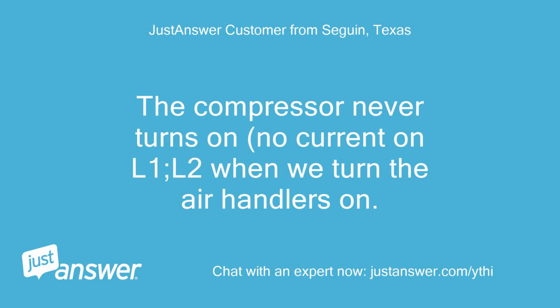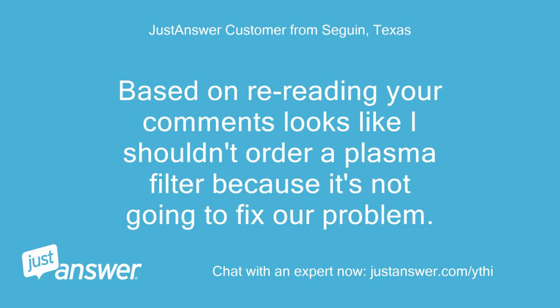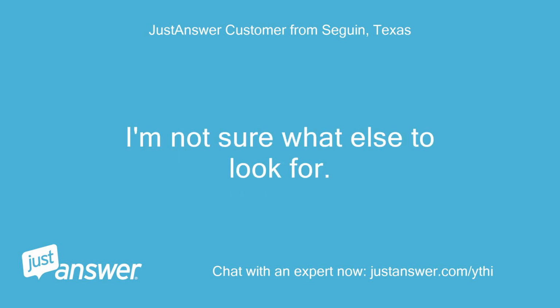The compressor never turns on, no current on L1, L2 when we turn the air handlers on. Air handlers run for 15 seconds blowing air, then the plasma LED begins to blink 5 times. Based on rereading your comments, looks like I shouldn't order a plasma filter because it's not going to fix our problem. I'm not sure what else to look for.